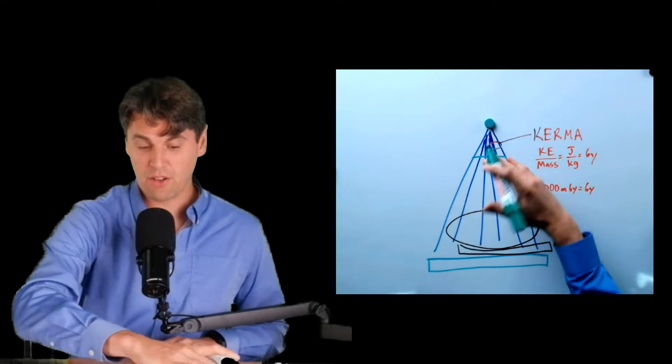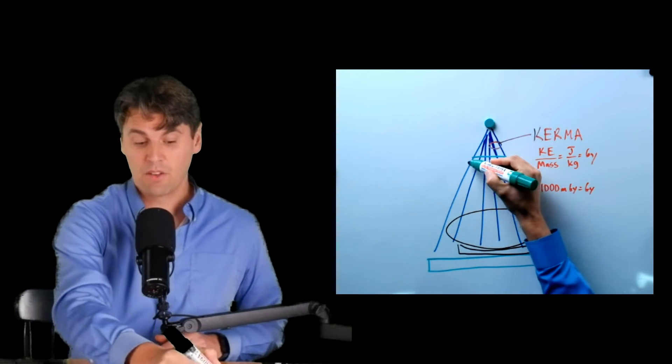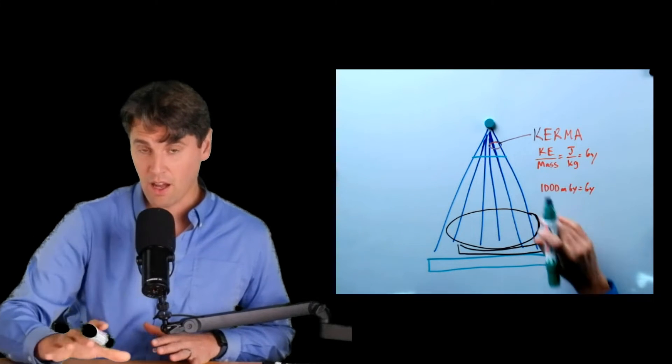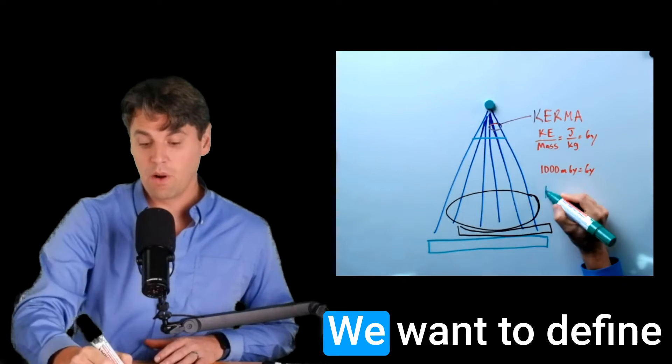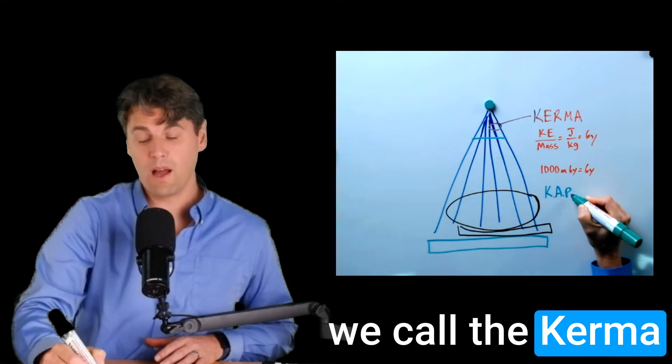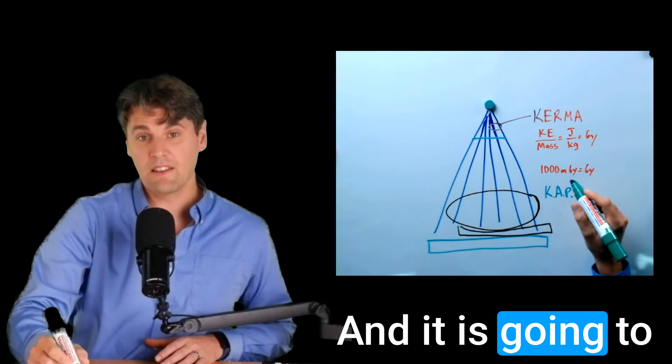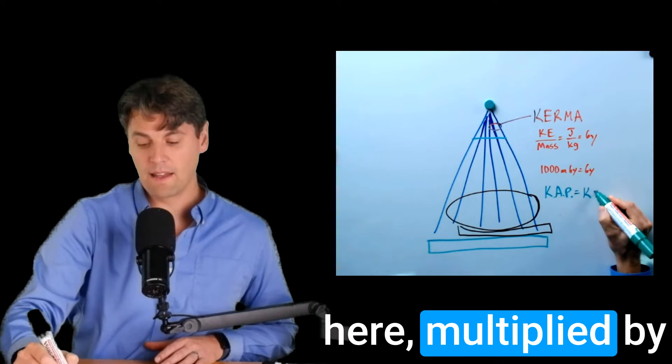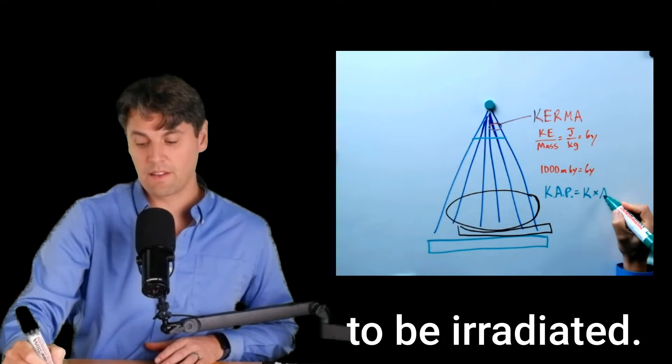Remember, we're just drawing this two-dimensional slice of our x-ray beam. So if we draw one line here, that's representing the area which is going to be irradiated by our x-ray beam. We want to define is this product that we call the Kerma area product, and it is going to be just that we talked about here multiplied by the area that's going to be irradiated.